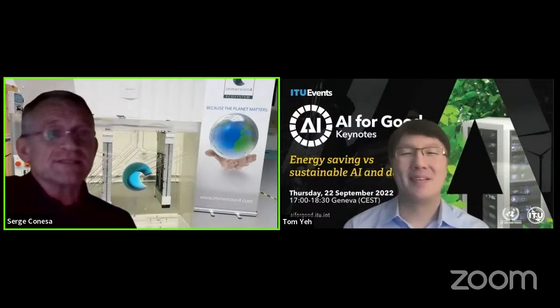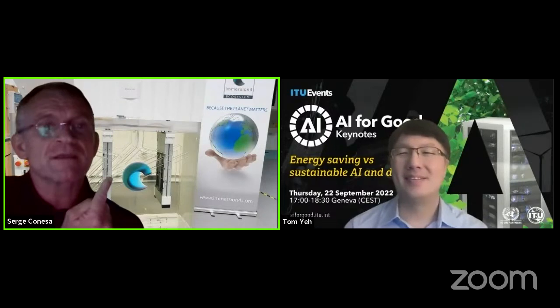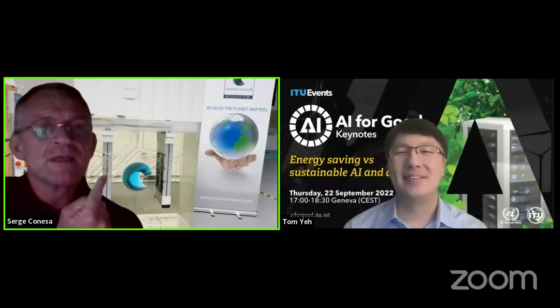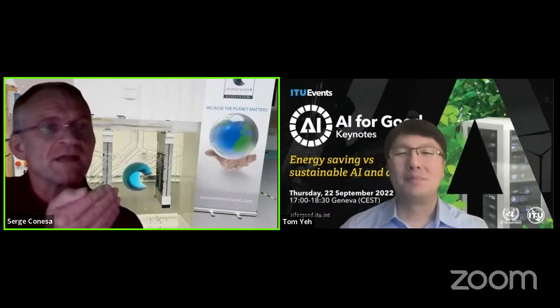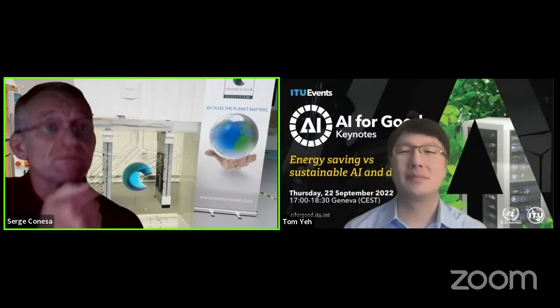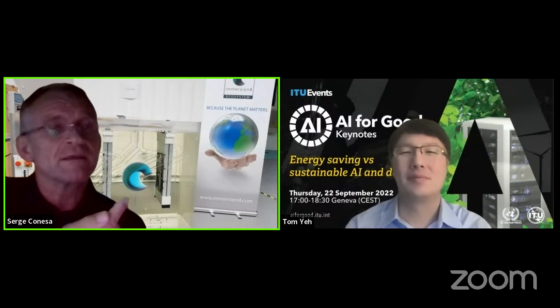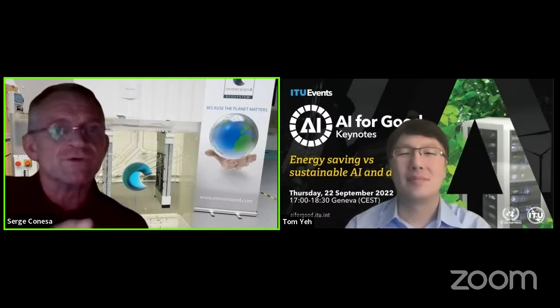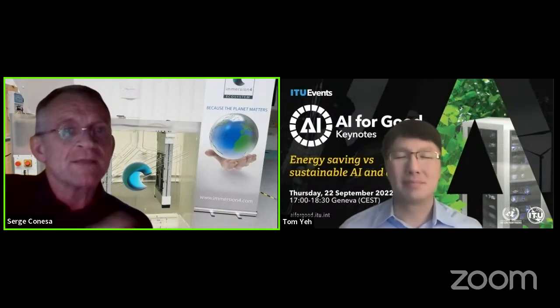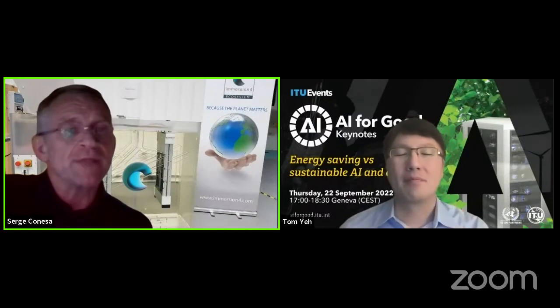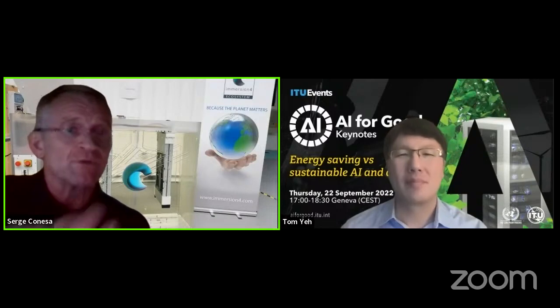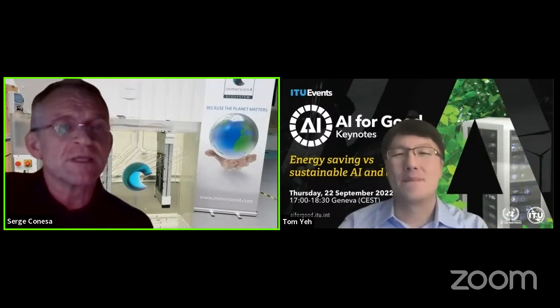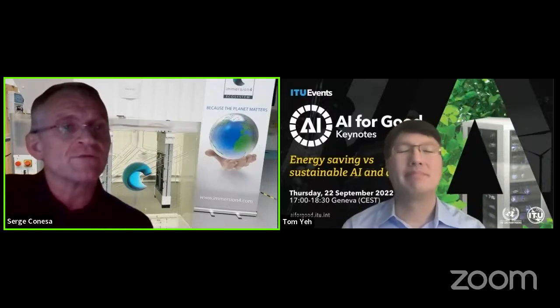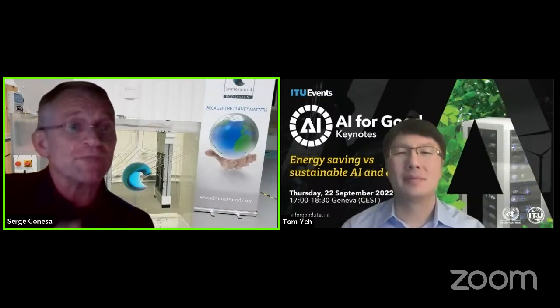Absolutely. As you can see on the back, we have a system in our lab, put clearly on the floor, with servers inside, no temperature control outside, but liquid temperature controlled. That's where we make the entire change. Through that liquid circulating, collecting the heat generated by the electronics, no matter if the server is idle, clocked, or overclocked, no matter the application, AI or mail servers or whatsoever, we just need to make in that room what we call a water loop, and through that water loop collect the calorie within our system, which we call DTM, dynamic thermal management system, in order to keep the temperature steady at the level the data center operators want.